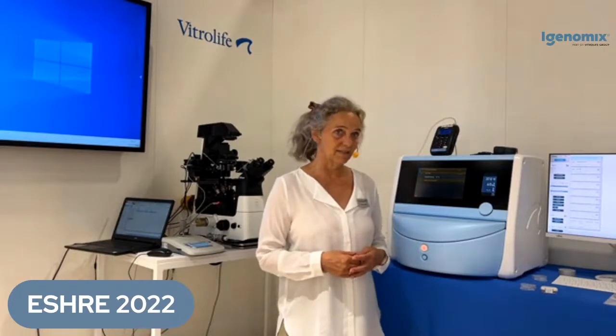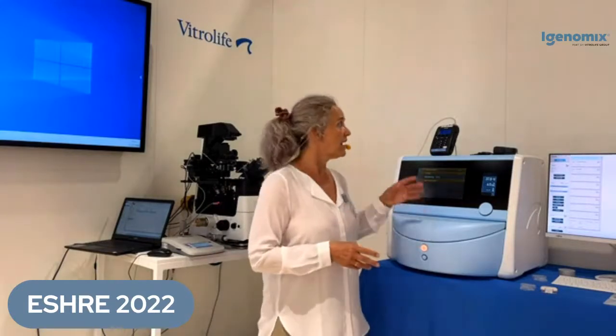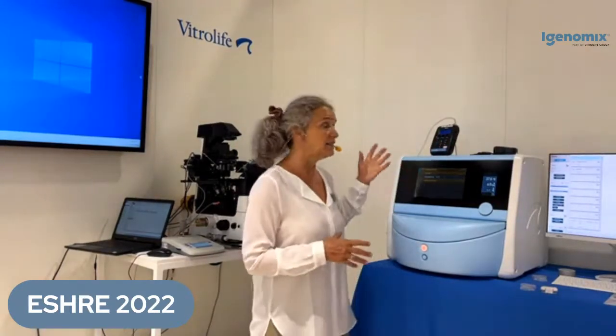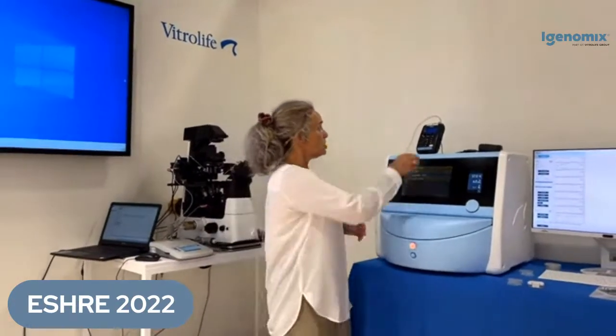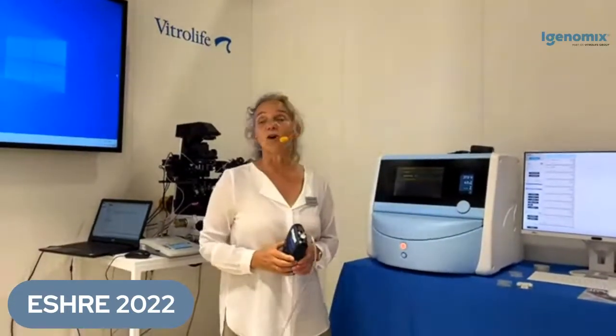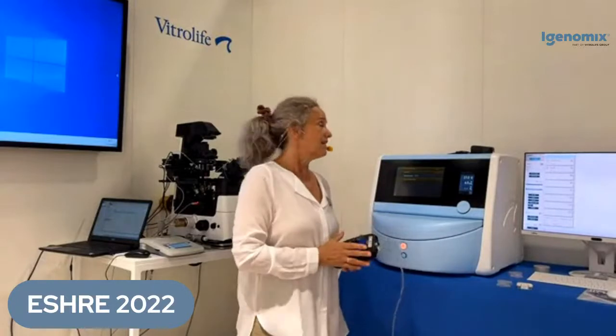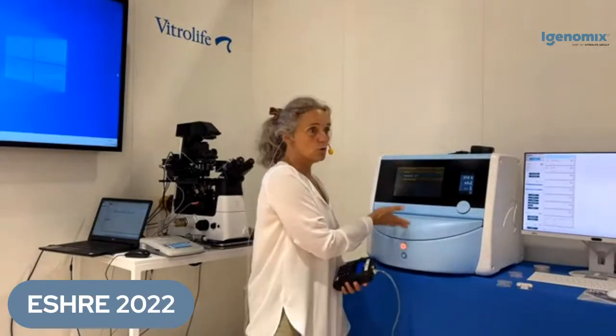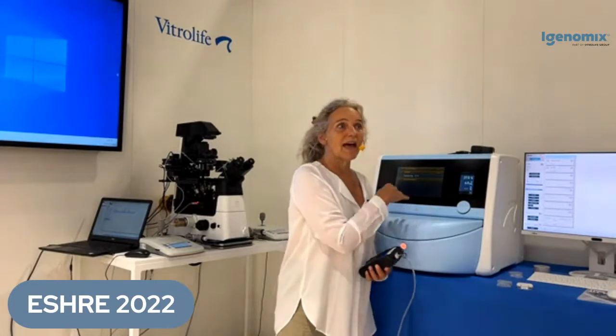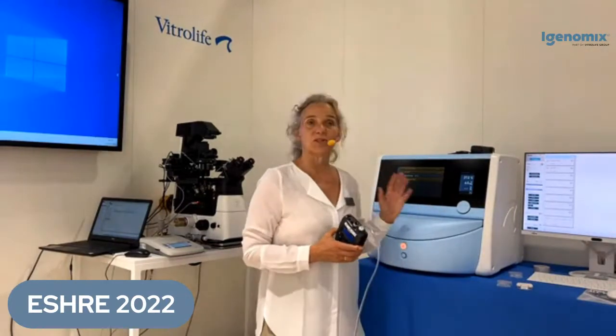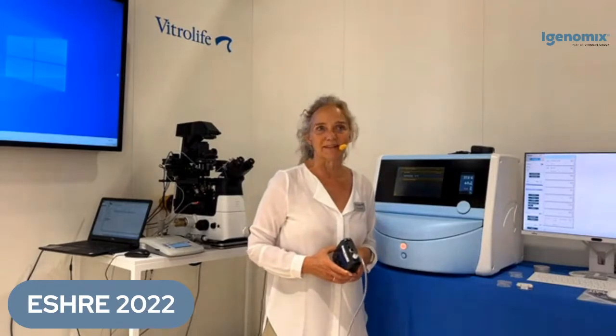It depends on your standard operating procedures how often you perform this, but Vitrolife still recommends that it be performed at least every 14 days. Before you start doing your validation and calibration, it is important that the analyzers you are using are newly calibrated to ensure an accurate measurement. We will start with the validation of CO2, because if we start with the temperature measurement, we need to open up the load door for inserting the probe, and we want to measure when it's absolutely stable. So of course you do it also in the morning.